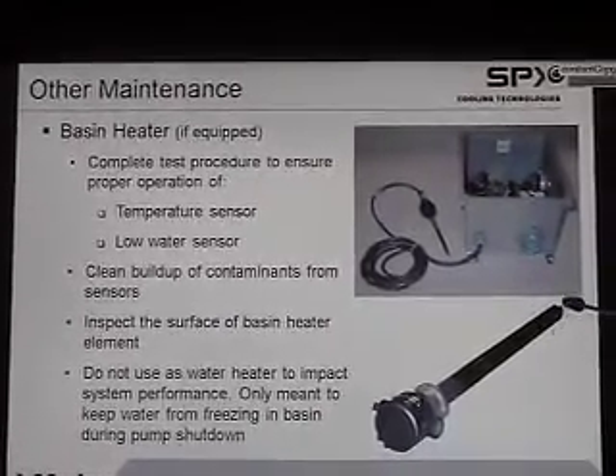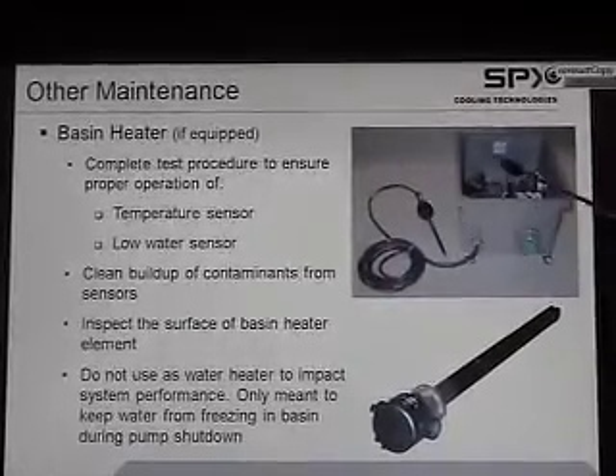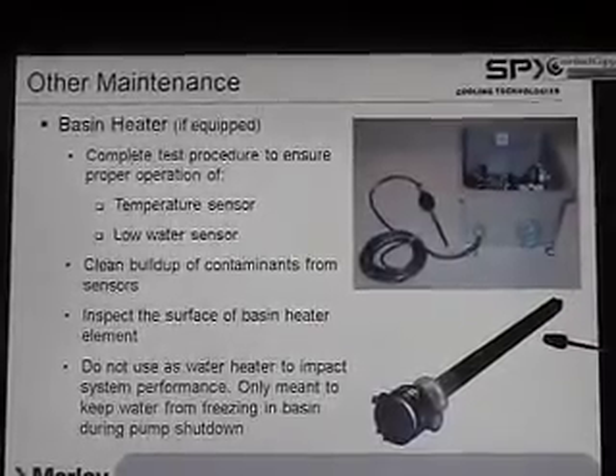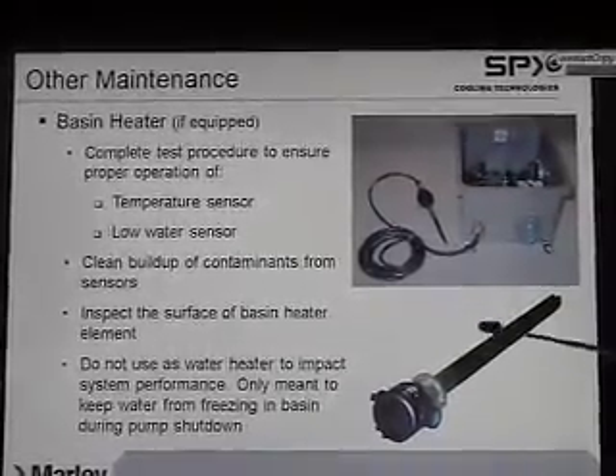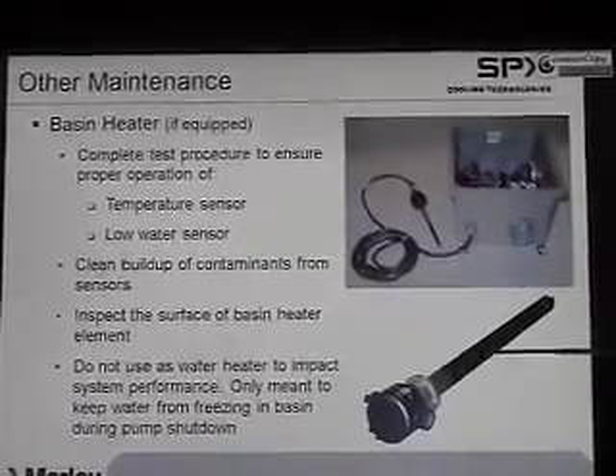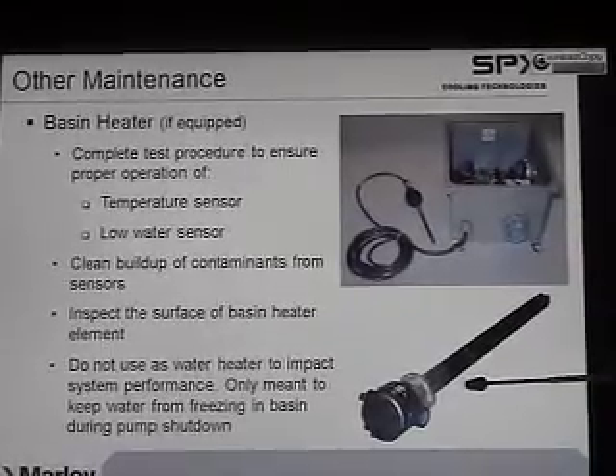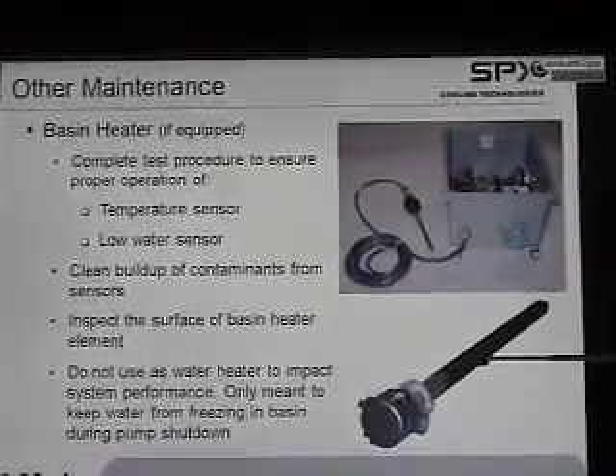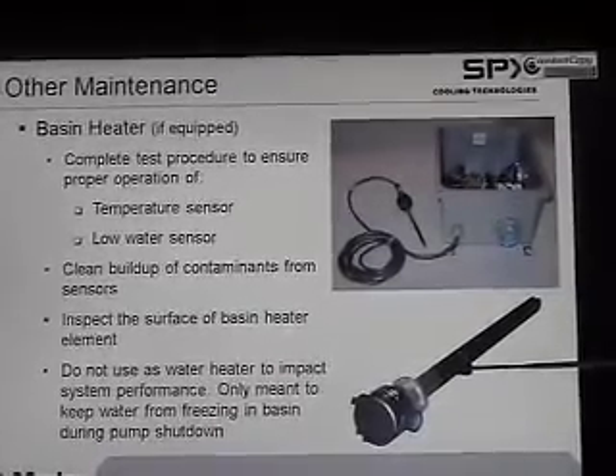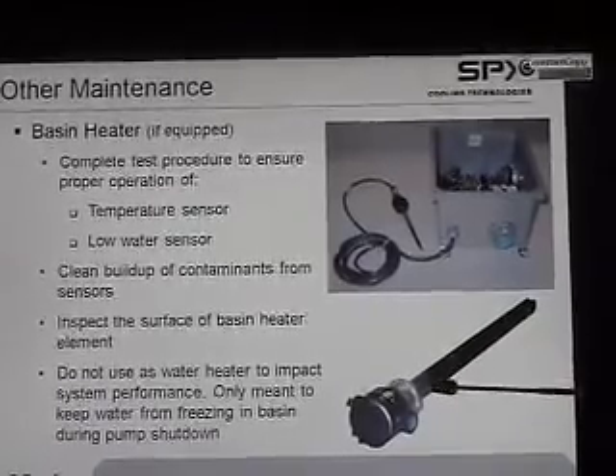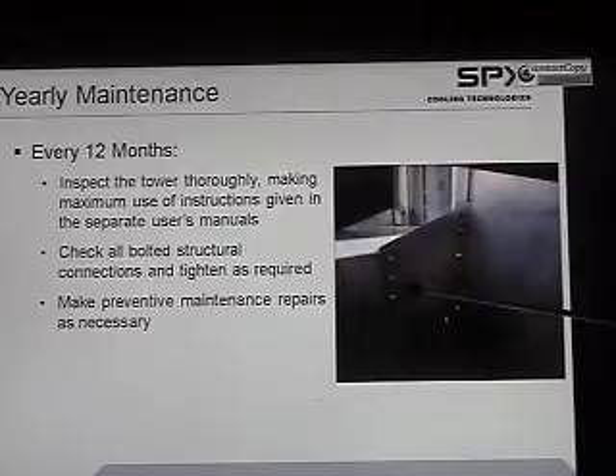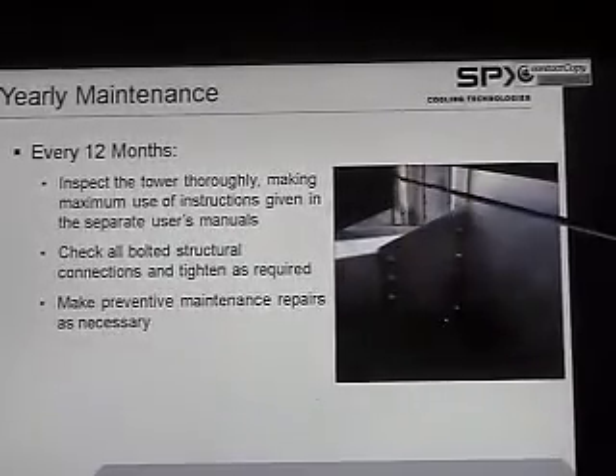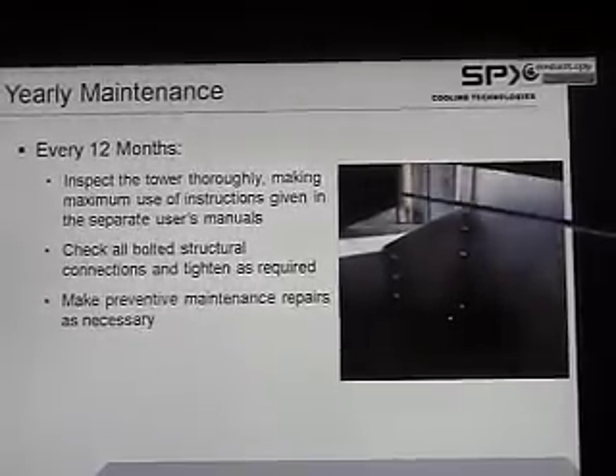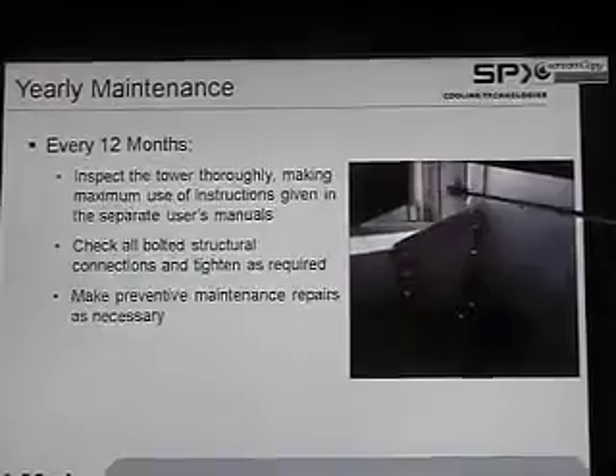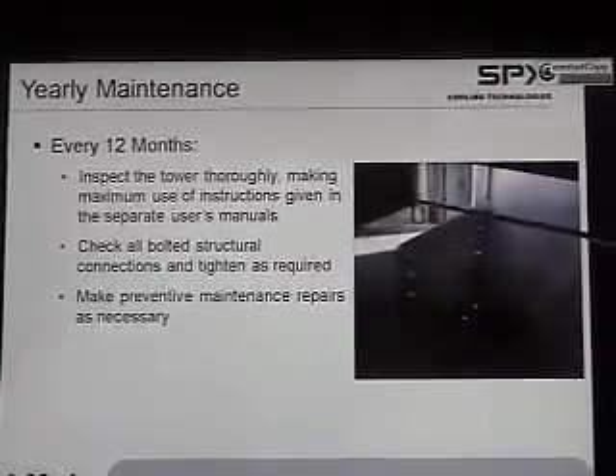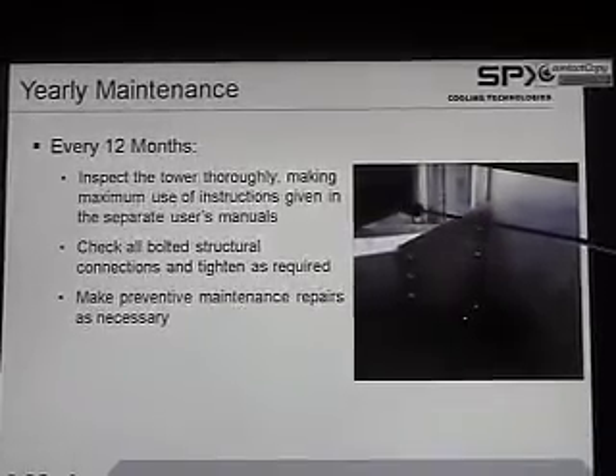You guys have a basin heater. It includes a probe, the control panel, and then this is the element. The basin heater is designed to keep the cold water in the cooling tower basin at about a 40-degree temperature when it's shut off. And then every 12 months there is a checklist in the user manual. Again, one of the big things is double checking to make sure that your structure is all bolted, and then complete your necessary repairs.